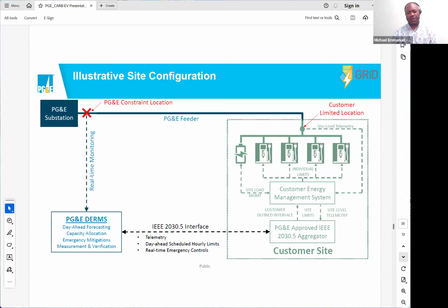One requirement is eligible flexible load. Number two, a customer energy management system at site that manages consumption. Number three, once you agree with the result of our analysis, you have to talk to a PG&E approved aggregator. We have a list of aggregators you have to work with. Their function is that for some sites, they speak a particular communication protocol, maybe Modbus, while our DERMS speaks IEEE 2030.5 protocol. So the aggregator helps translate the message from one protocol to a compatible language at site.